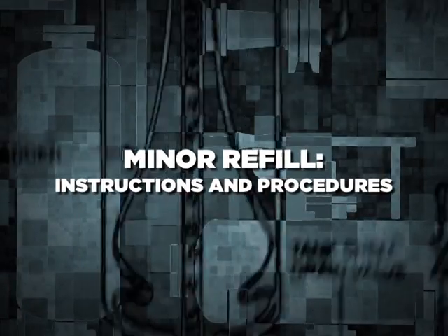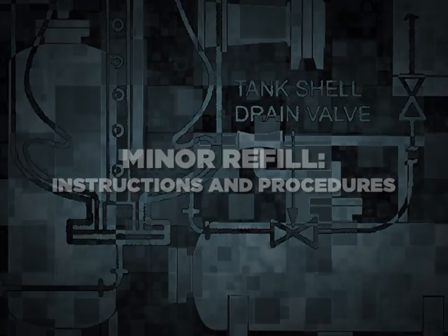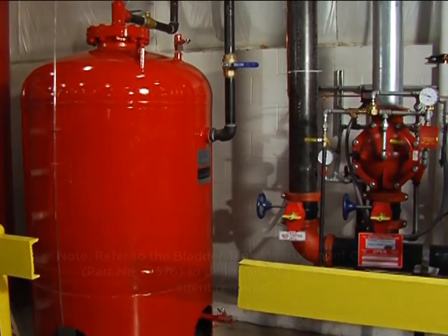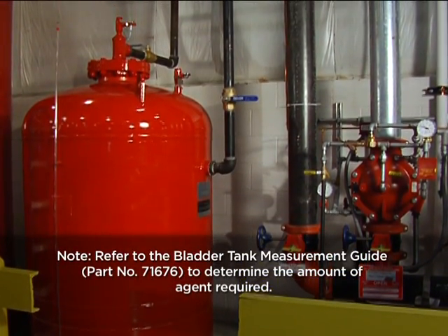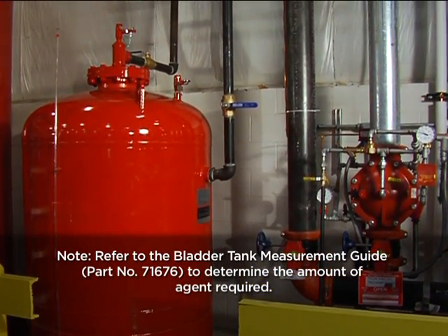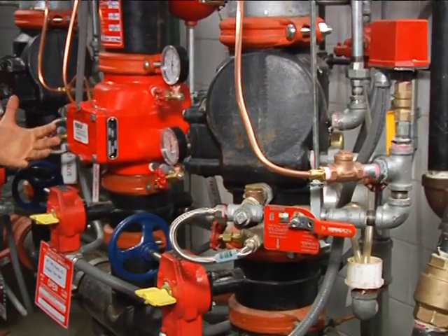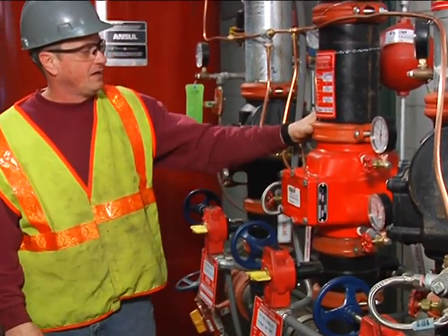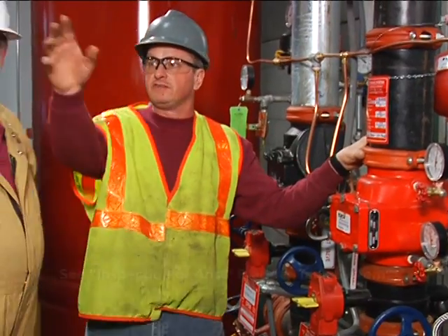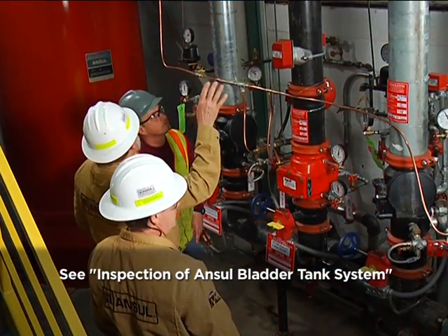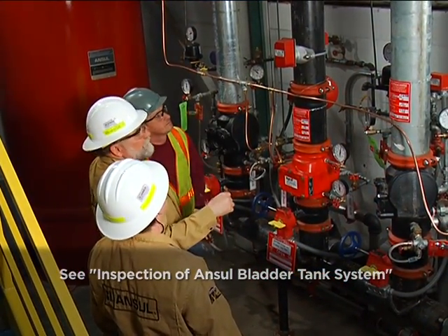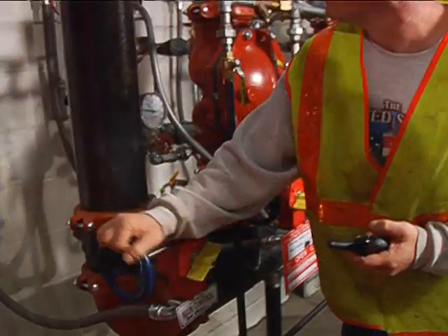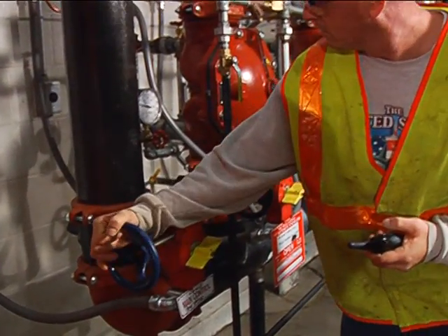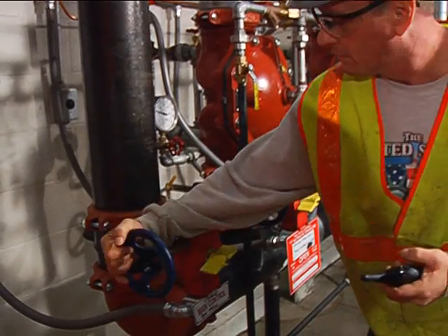Minor or partial refill instructions and procedures. A minor refill is required when less than 25% of the concentrate must be replaced within the bladder tank. Before you proceed with your minor or partial refill, Ansul recommends performing a complete inspection of your Ansul bladder tank system. If the system was partially discharged, make sure to turn off the water pressure to the bladder tank.